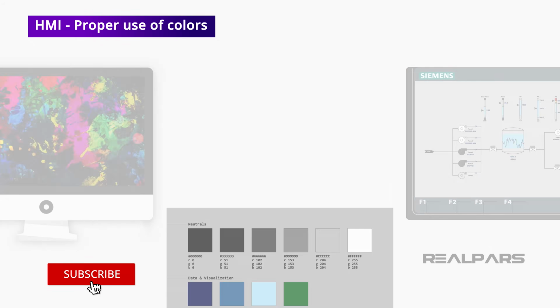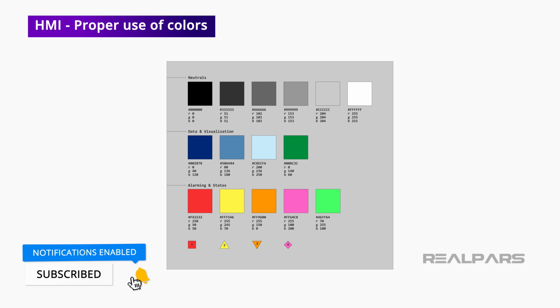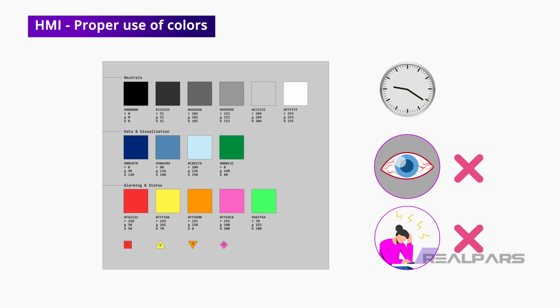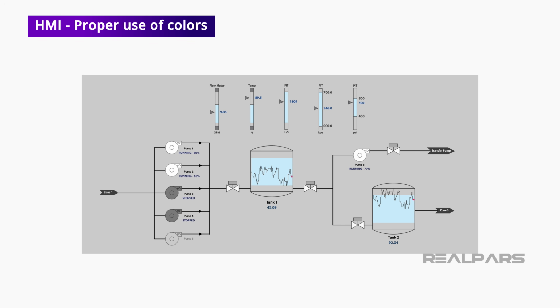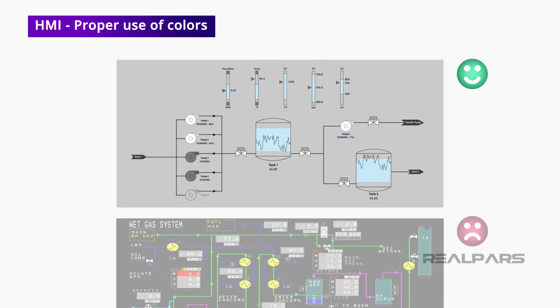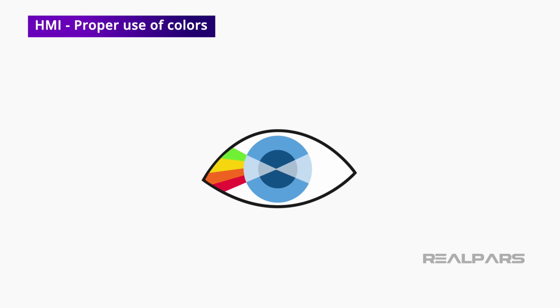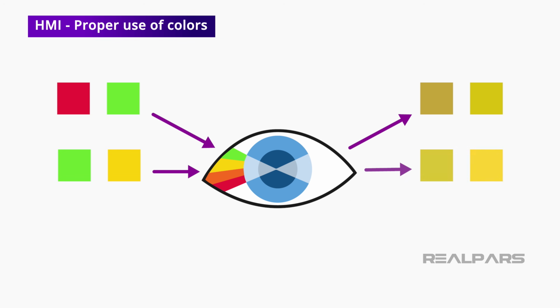Another very important reason for a color palette is to reduce visual fatigue and illusions from long hours of viewing in HMI that uses bright and contrasting colors that is prevalent in many HMI applications. Remember that we are designing an HMI that follows a user's mental model and workflow, so there is minimal need for color as it draws attention, and the goal is to reduce the visual clutter that comes with high-intensity colors. When we are talking about the user experience in an HMI, remember that there are users who are color impaired, thus making the visual differences between red-green, green-yellow, and white-cyan particularly difficult for them.